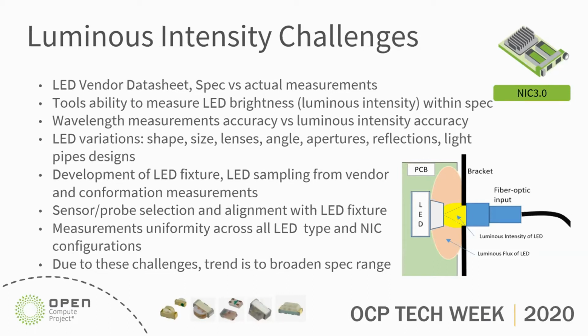Sensor probe selections and alignment with LED fixture. Research showed, with experimentation on LED fixture, that sensor probe selection, with the necessary mechanical and optical alignment, is a very important aspect prior to any measurements on LEDs.